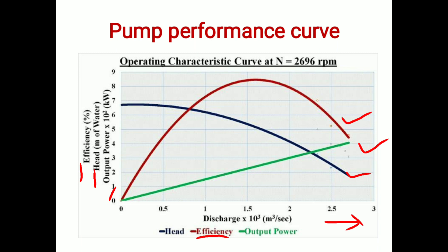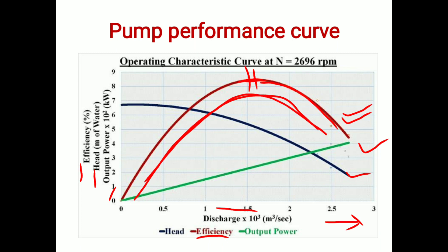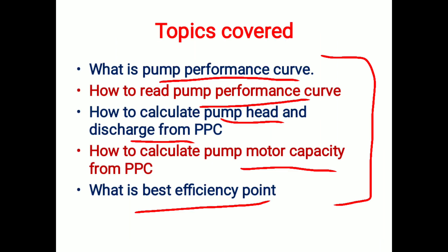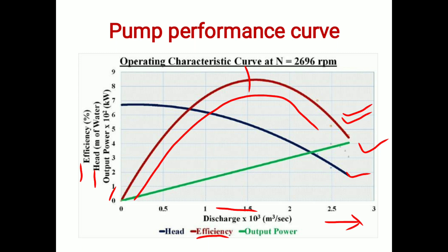On the y-axis we are plotting three parameters: efficiency, head, and output power. The first curve is the efficiency curve — the red one. The efficiency curve is a parabolic-like curve. This curve indicates that when we increase pump flow, pump efficiency increases, attains its highest point at a certain flow, and after that when we further increase discharge, efficiency decreases. This highest point is called the best efficiency point.